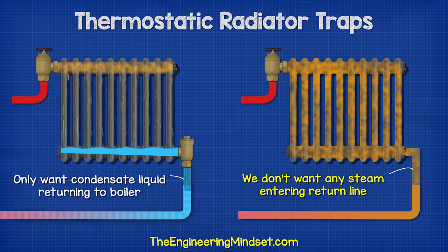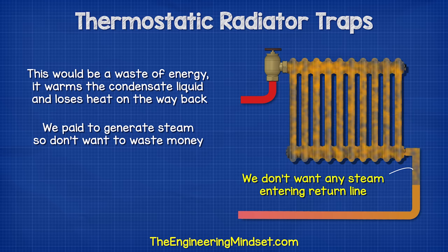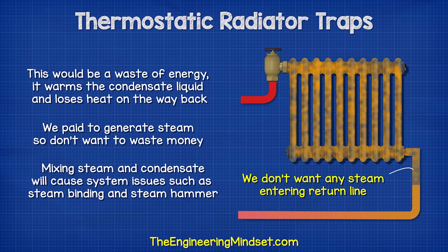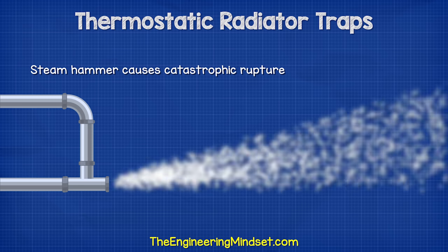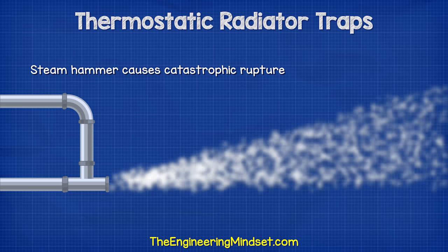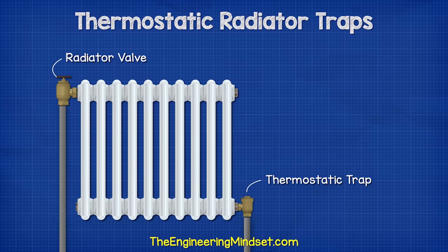We only want condensate liquid returning to the boiler — we don't want any steam getting into the return line. That would waste energy by warming the condensate and losing heat on the way back. Mixing steam and condensate also causes many problems such as steam binding and steam hammer, which can be catastrophic for the system. One way to prevent this is through a thermostatic radiator trap.